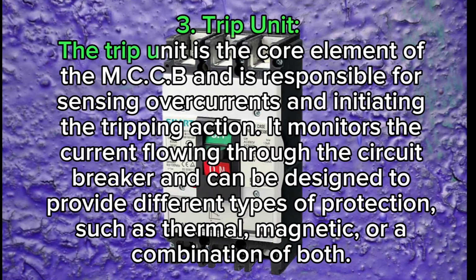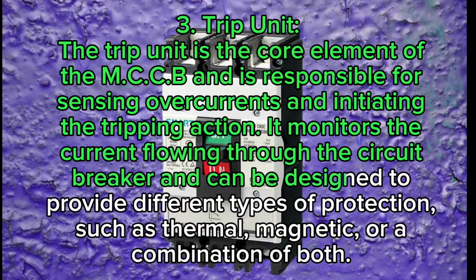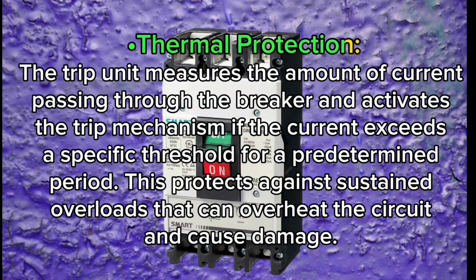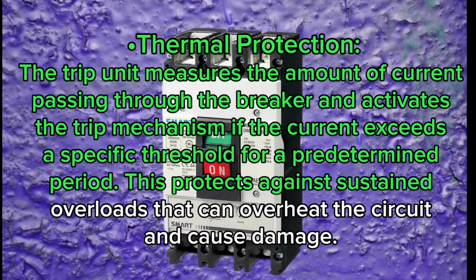3. Trip unit. The trip unit is the core element of the MCCB and is responsible for sensing overcurrents and initiating the tripping action. It monitors the current flowing through the circuit breaker and can be designed to provide different types of protection, such as thermal, magnetic, or a combination of both. Thermal protection. The trip unit measures the amount of current passing through the breaker and activates the trip mechanism if the current exceeds a specific threshold for a predetermined period. This protects against sustained overloads that can overheat the circuit and cause damage.